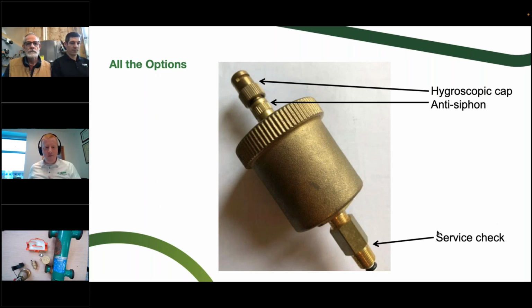Now, that service check valve, what happens with that guy is as you thread on the air vent, it actually pushes a check valve open, allowing it to be open to the system. And as you start to unthread it again, it'll actually close off so you can service that air vent, replace it, do whatever you need to do without taking a bath or doing the famous hot swap where you're trying not to take a bath, or lowering the pressure or whatever. That service check valve is great because it's very small. It doesn't take up a lot of room. And the fact is you can still service it without taking down the system. So I hope that answers that particular question.